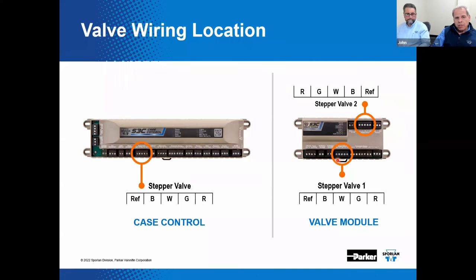And if you're using a valve module, and if you happen to have an EEPR in conjunction with maybe an EEV, that EEPR would need to be landed up here at the stepper valve 2 location. Correct. This is just a requirement. That is, if you have a valve module that is going to be the control that's telling it what to do, and you've used this position for maybe an EEV.